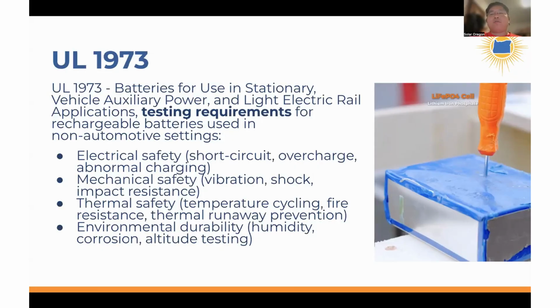But in addition to electrical safety, there's also in this test standard a test for mechanical safety - like if you were to drop the battery, or it's subjected to vibration, or especially for outdoor batteries, under extreme heat or extreme cold, is the battery going to do unexpected things? This UL test will ensure there's safety within the designed parameters and under unexpected conditions.